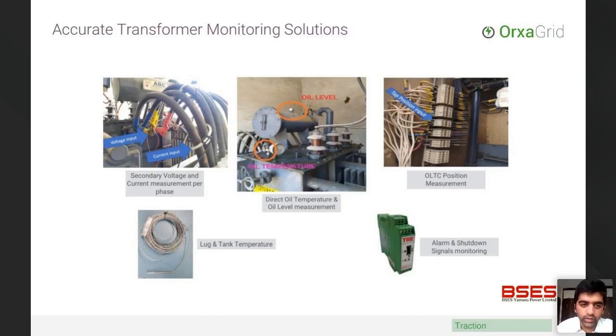So the best way to do this is by using a Rogowski coil, which provides you the flexibility of clamping onto any tight network. But not only flexibility of clamping, it also provides very high measurement range without the problem of saturation. If you implement a CT, there's a big chance that the CT will get saturated at high currents, whereas a Rogowski coil will also allow you to do fault current measurements. You can go all the way up to 10,000 amperes with Rogowski coils as well.